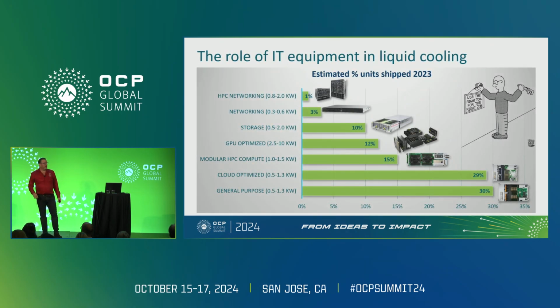Does it mean we're going to have to cool all systems with immersion cooling? No, because immersion is not for everything, just like cold plate is not for everything. There's plenty of stuff out there, even on this exhibition floor, where everything is focused on high density equipment, and plenty that doesn't need liquid cooling at all. Is it going to replace cold plate cooling? No, not either.